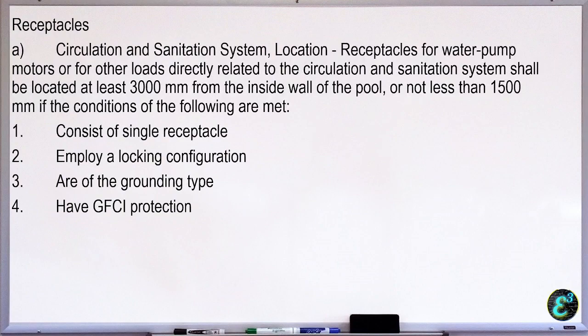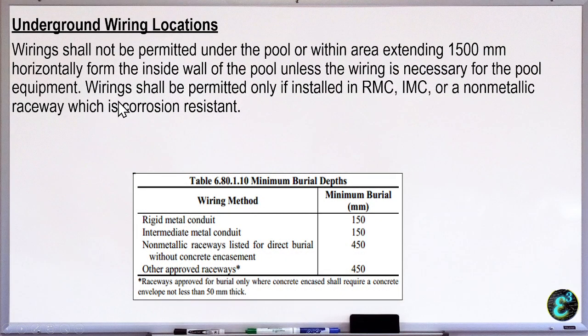I will not go through the table for now. Okay, so wiring shall be permitted only if installed in RMC, IMC, or non-metallic raceway which is corrosion resistant. What is allowed is wiring that is necessary for the pool equipment, but only if installed in RMC, IMC, or corrosion resistant non-metallic raceway. So these are the minimum burial lengths. For RMC, 150 mm. For IMC, steel, 150 mm. For non-metallic raceway listed for direct burial without concrete encasement, it is 450 mm. For other approved raceways, it is also 450 mm.